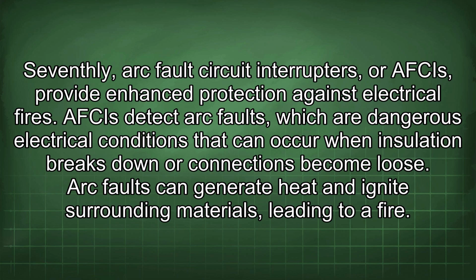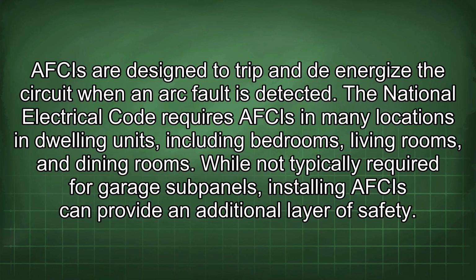Arc faults can generate heat and ignite surrounding materials, leading to a fire. AFCIs are designed to trip and de-energize the circuit when an arc fault is detected. The National Electrical Code requires AFCIs in many locations in dwelling units, including bedrooms, living rooms, and dining rooms. While not typically required for garage subpanels, installing an AFCI can provide an additional layer of safety.